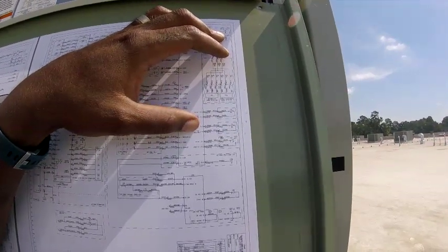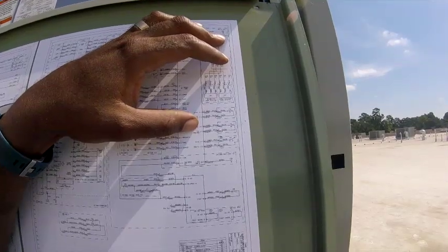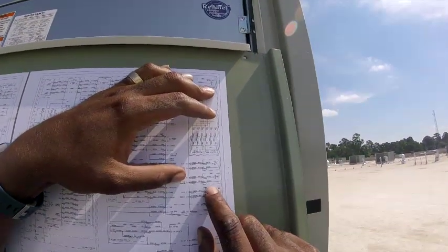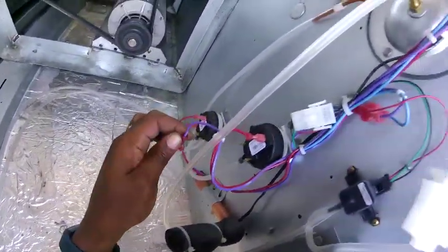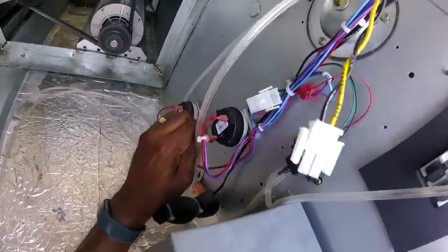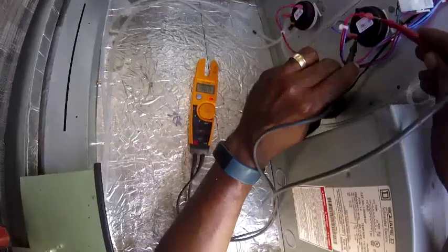Should be normally closed. And it was closed, but hook it up, it goes off in alarm. So it says a purple wire 101C. Purple wire, yeah, it's 101C right there. It should be normally closed, but when I hook it up, it's gonna go in alarm. It's closed.